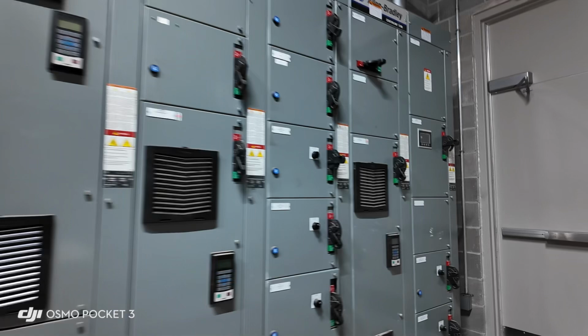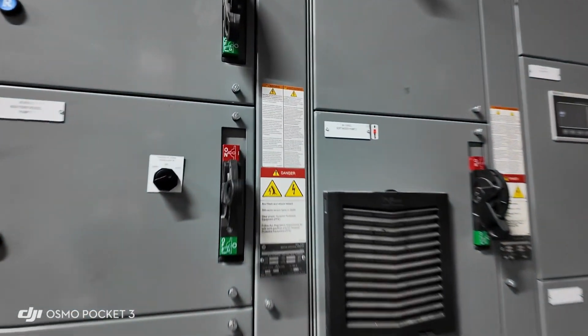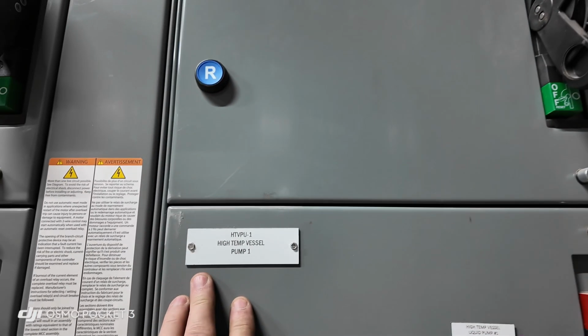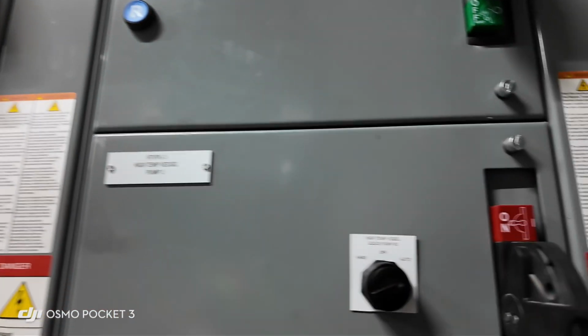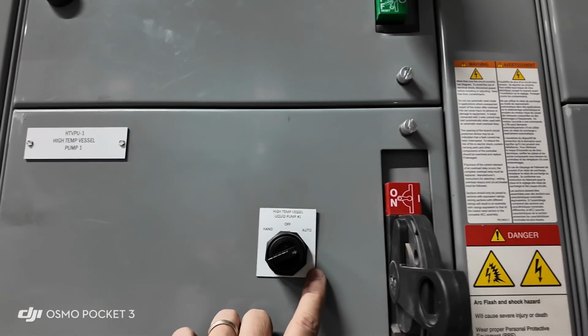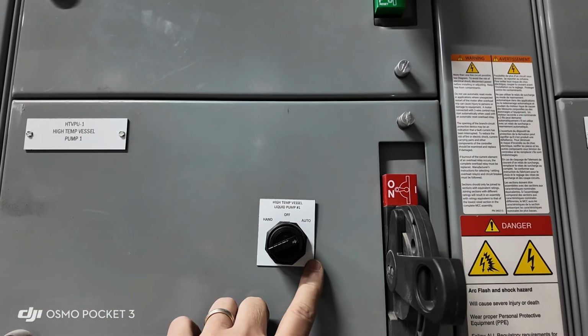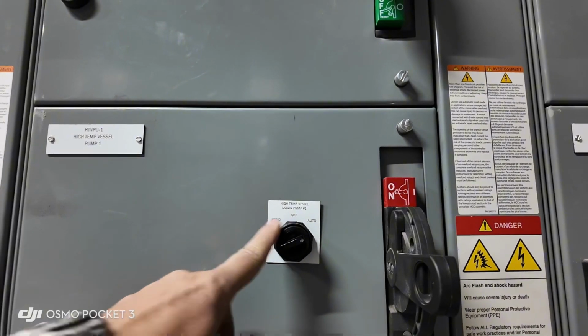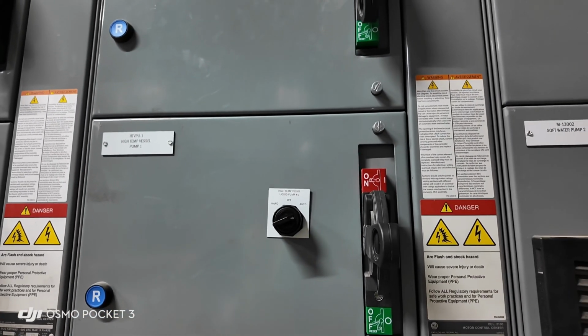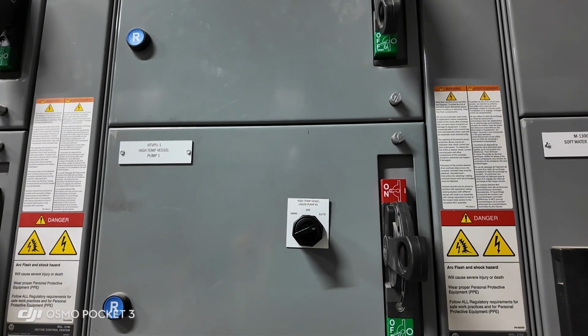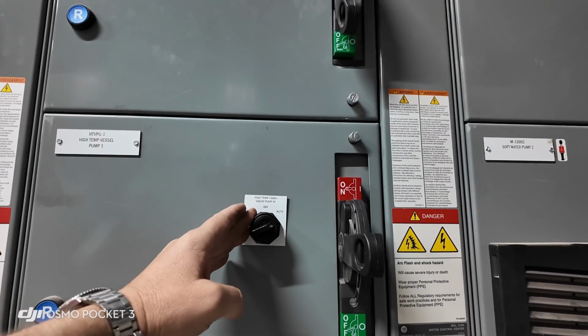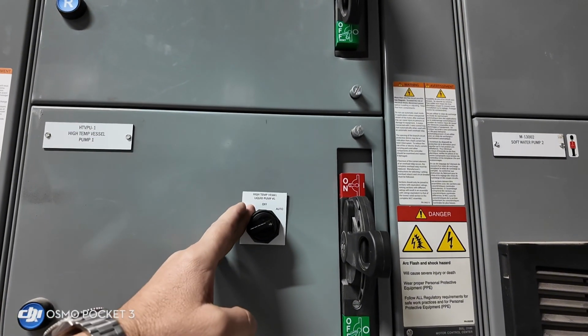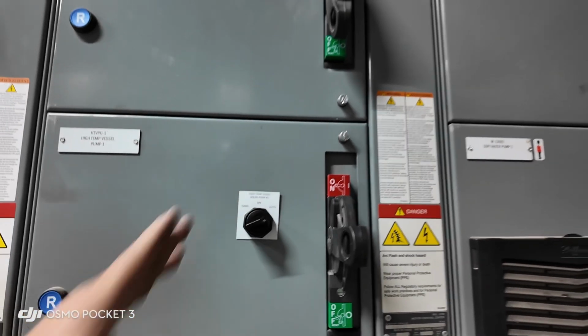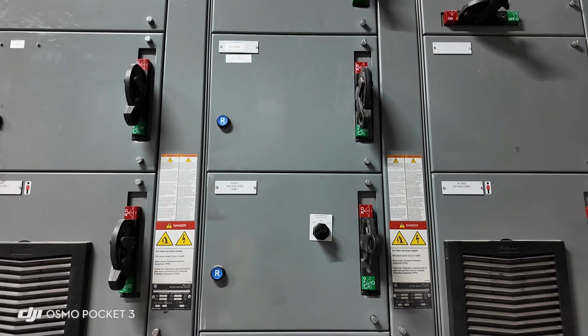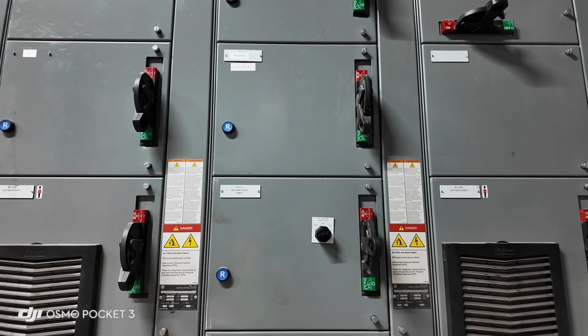Okay, I'm going to walk you over and show you the Smart Motor Control Center here. On the Smart Motor Control Center, you can see here we have high temp vessel pump 1. It has a hand-off-auto switch in it. It should normally be in the auto position. Okay, off, if we wanted to turn the pump off, that will give us alarms over there at the control panel. Hand is for no PLC operation. We would then need to turn the pump on in hand. The pump is still protected from low level shutdown by a mechanical float.